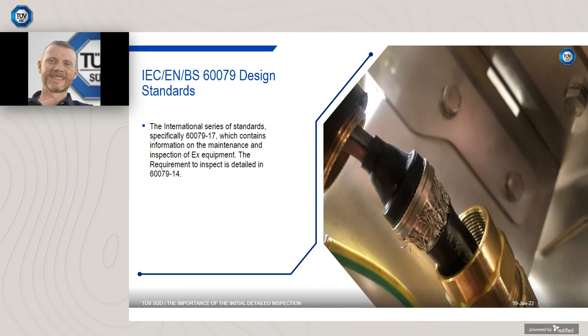IEC EN BS 60079 design standards. The international series of standards, specifically 60079-17, contains information on the maintenance and inspection of Ex equipment. The requirement to inspect is detailed in 60079-14. Standards, harmonised, designated standards, or otherwise, are known as recognised good practice. They are used as benchmarks for regulatory authorities and auditors such as the HSE.